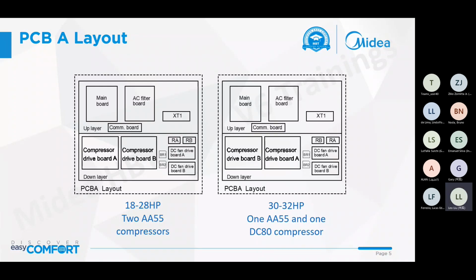The right side is for the big size outdoor unit, 30 and 32 horsepower. These two units adopt one big volume compressor and one small volume compressor. So there are two types of compressor, and the compressor drive board is different. The quantity is the same, just the size is different.